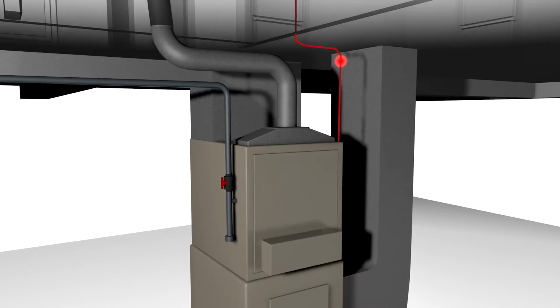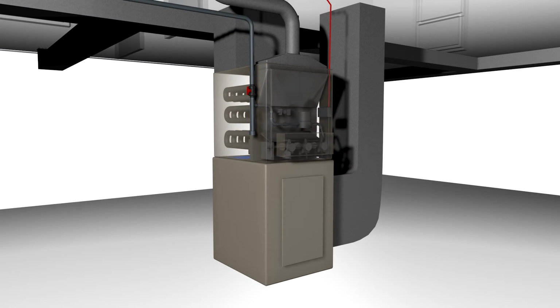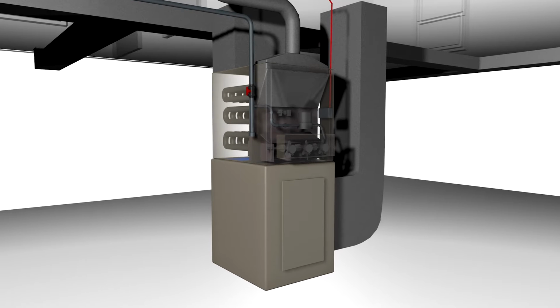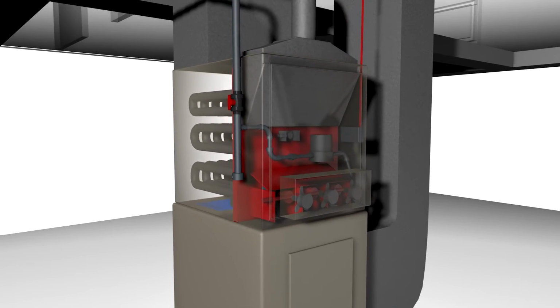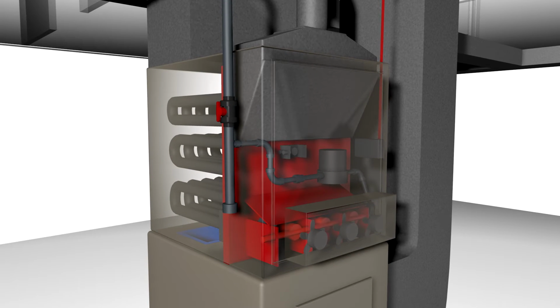Your furnace does several things simultaneously when it receives the signal to start the cycle. The gas valves open, the burners are ignited, and the blower turns on. The burners in your furnace are similar to the burners on a gas grill. They're a set of tubes through which the natural gas enters the furnace and is burned. The flames are initiated and controlled by an igniter, the gas valve, and flame sensors.